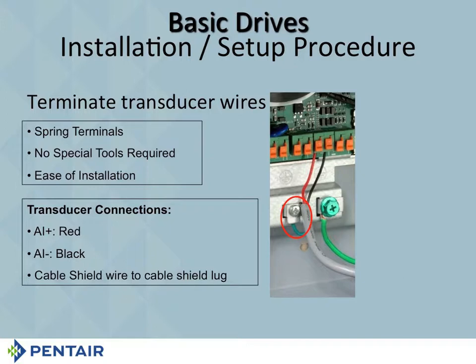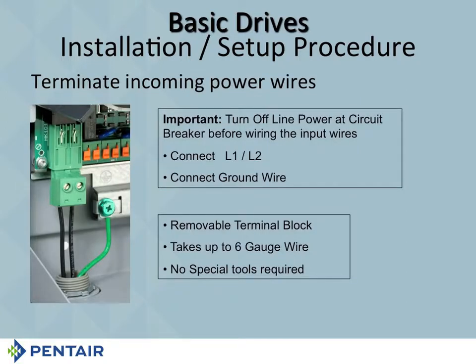Don't hook it up to the ground wire. Hook it up to the shield cable lug. And then on your input, you're going to have your L1 and L2 connections. Remember, you can pull that out and hook them up too. All right. Pull your wires through the round thing first. All right. And of course, don't forget to connect the ground.